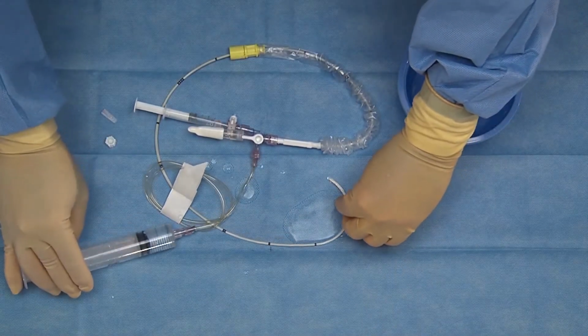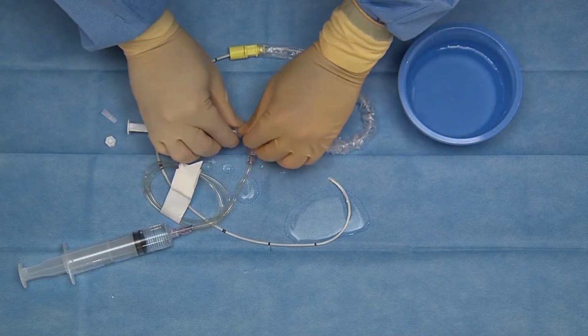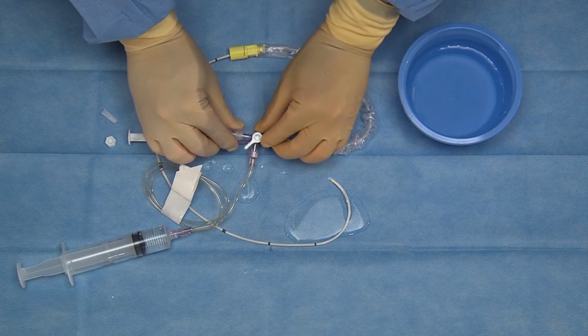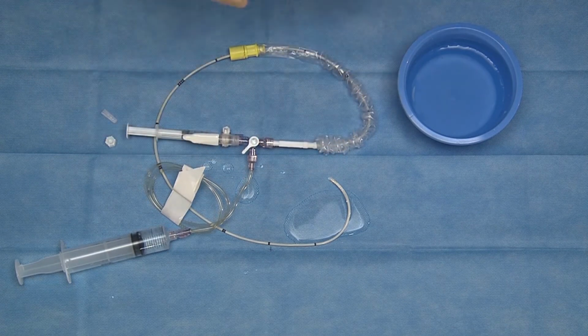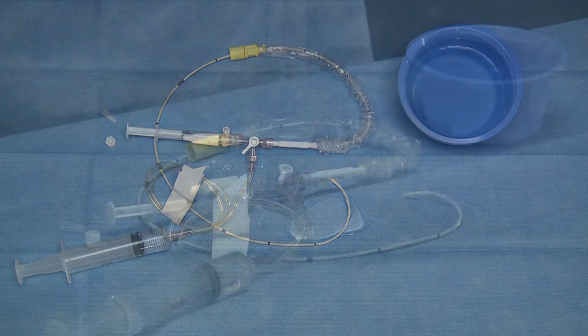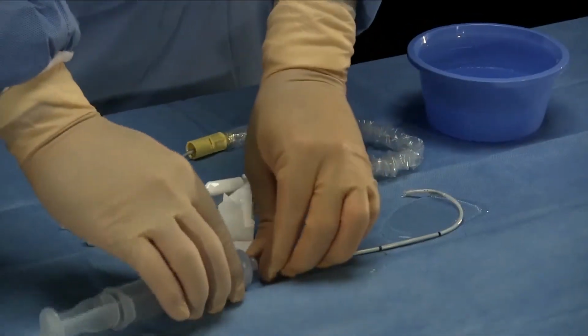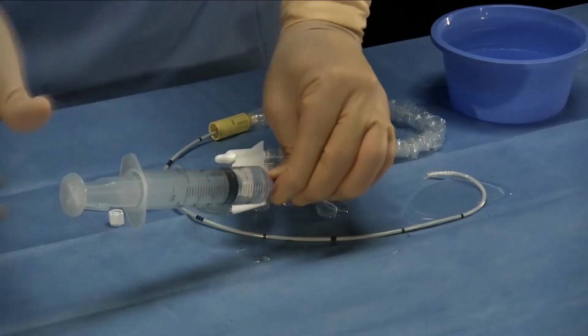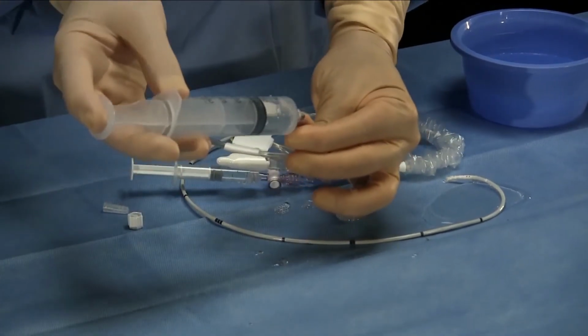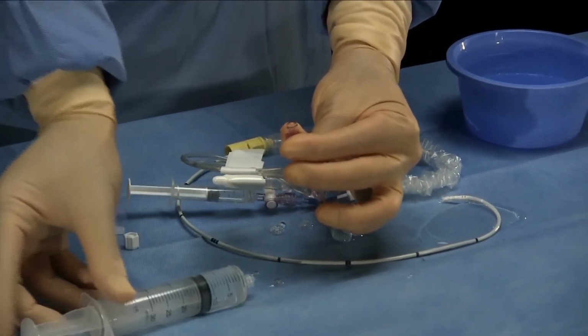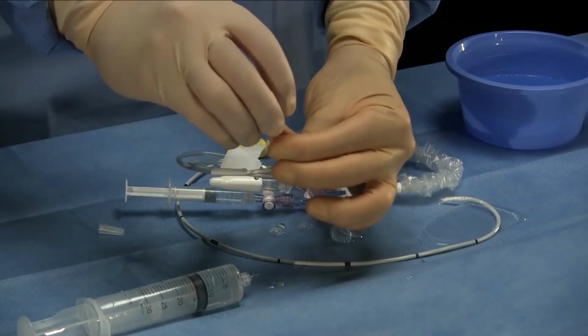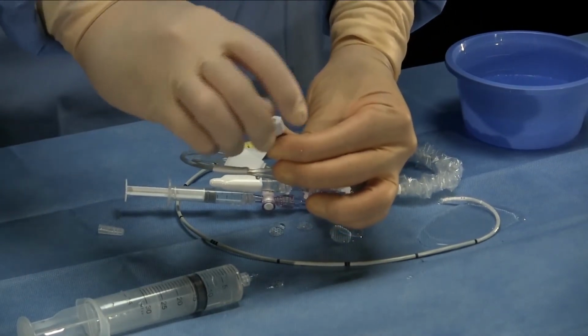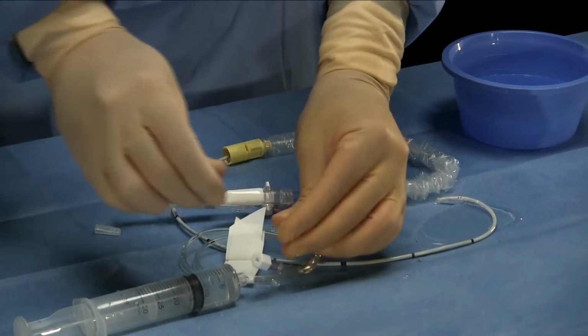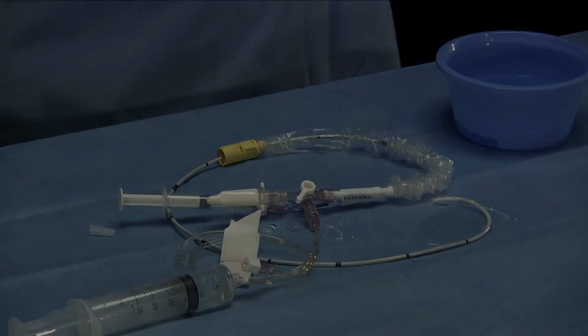Turn the three-way stopcock off to all three ports by positioning it at a 45-degree angle directly in between the hose barb port and the pressure line port. Disconnect the syringe and then wet fill and cap the pressure line. The EndoVent pulmonary catheter is now prepped and ready for use.